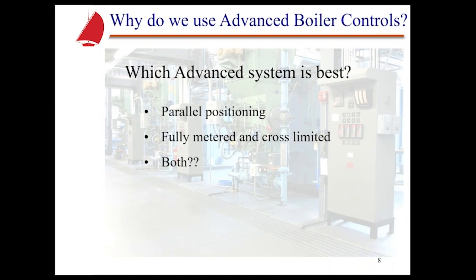And that will repeat, because once we put in these points from low fire to high fire, the system will extrapolate through those points, and there could be as many as 20, 24 points from low fire to high fire, and it will follow that curve, if you will, from low fire to high fire. Parallel positioning means that those servos are going to be moving in parallel to be at those points along that curve as it moves and modulates. If one lags the other and is not where it's supposed to be versus the lead servo, which in many cases will be the air servo, then obviously we will fault out because we don't have it in the position it's supposed to be in.